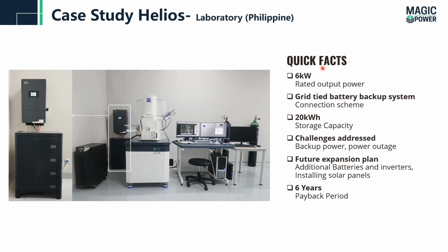If we look at the quick facts, the rated output power for the system is 6 kilowatts. Basically, the system is a grid-tied battery backup system at this stage because the solar panels are not connected to the system. The storage capacity is 20 kilowatt hours. The challenge addressed for the customer before installing the system was backup power. They require stable backup power, and there are a lot of power outages in that area.